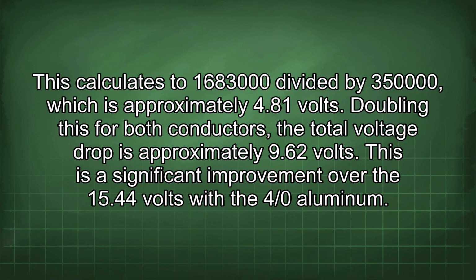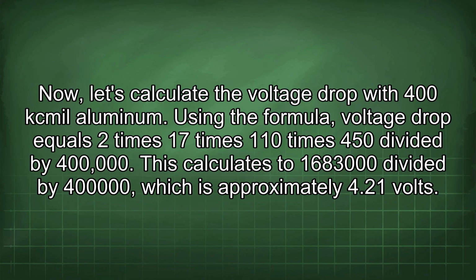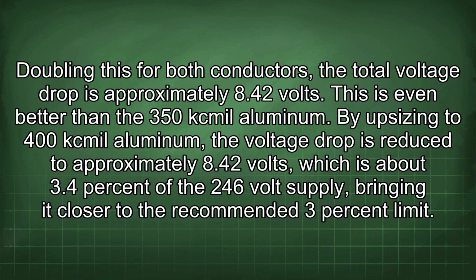Doubling this for both conductors, the total voltage drop is approximately 9.62 volts. This is a significant improvement over the 15.44 volts with the 4/0 aluminum. Now let's calculate the voltage drop with 400 kcmil aluminum. Using the formula, voltage drop equals 2 times 17 times 110 times 450 divided by 400,000. This calculates to 1,683,000 divided by 400,000, which is approximately 4.21 volts. Doubling this for both conductors, the total voltage drop is approximately 8.42 volts. This is even better than the 350 kcmil aluminum.